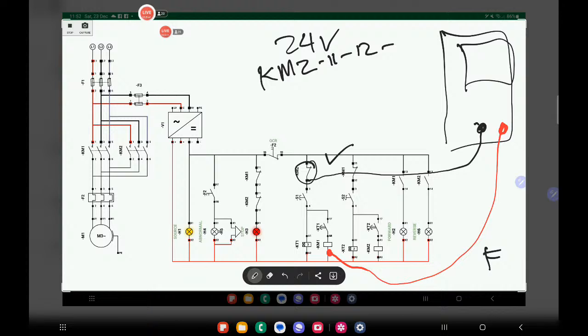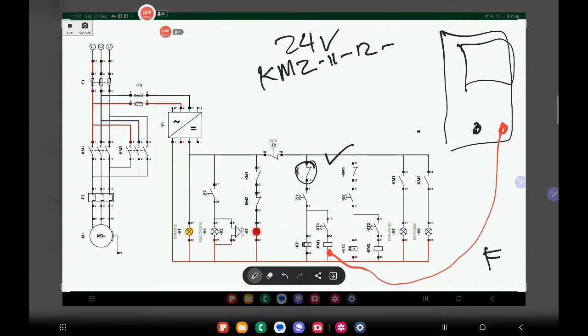And if I now move my probe after the S1 and I press S1 and I'm having 24 volts, that only means that my S1 is in good condition. But if I don't have 24 volts after pressing S1, then for sure your start switch is not closing. That is why you're not having a forward operation onto your system.